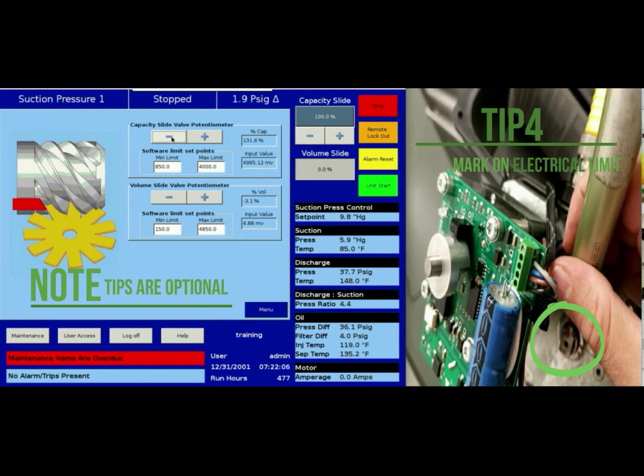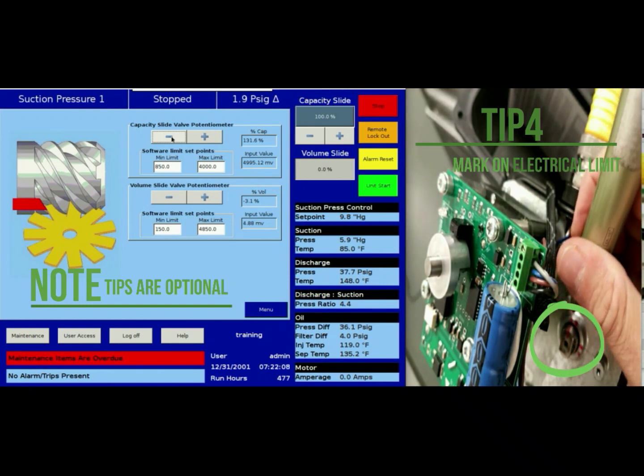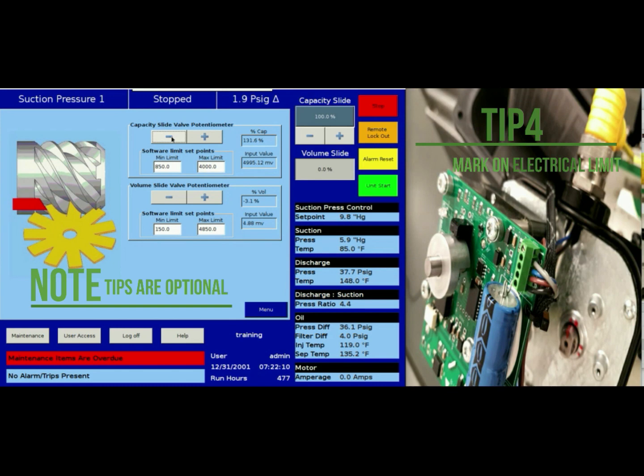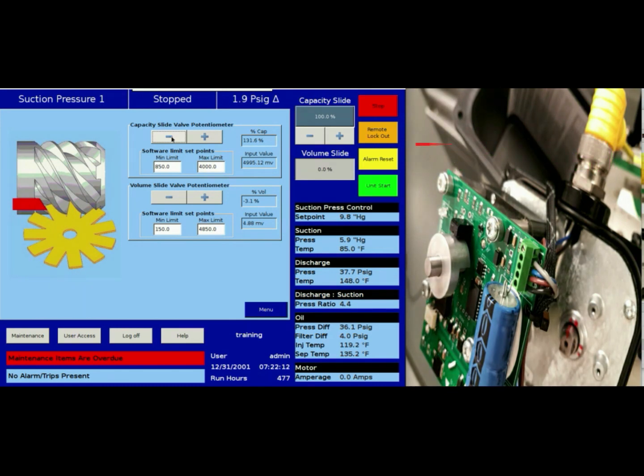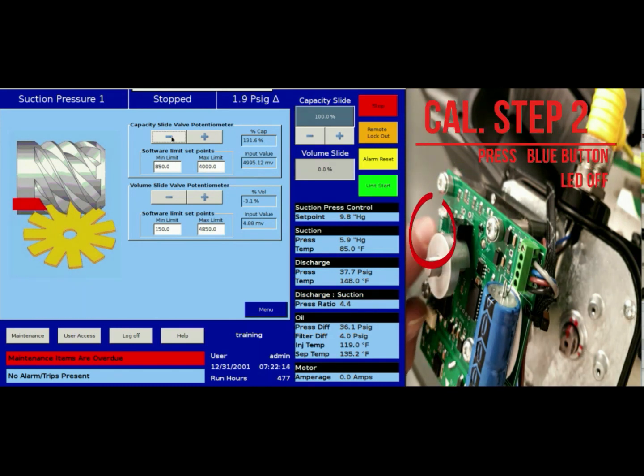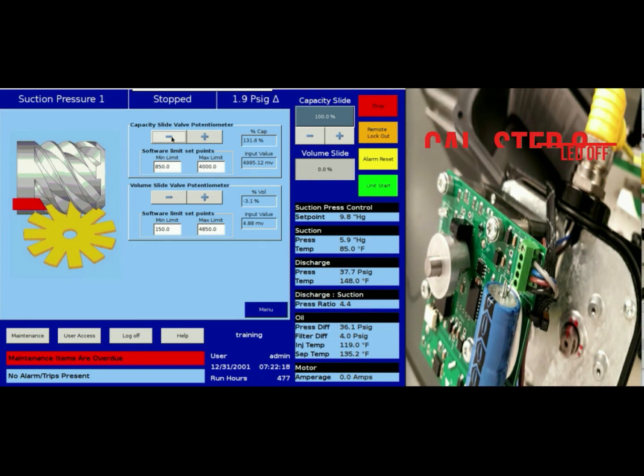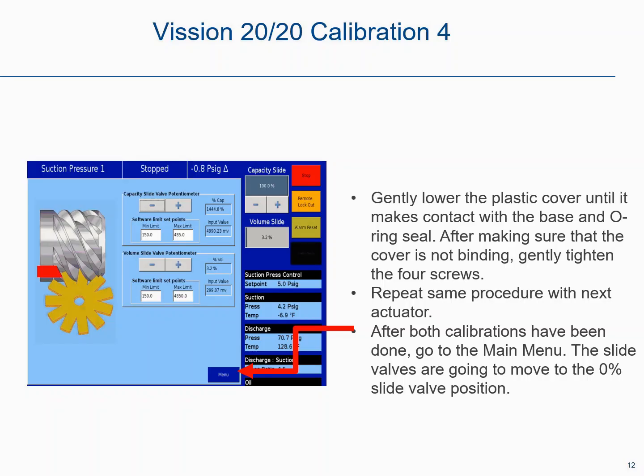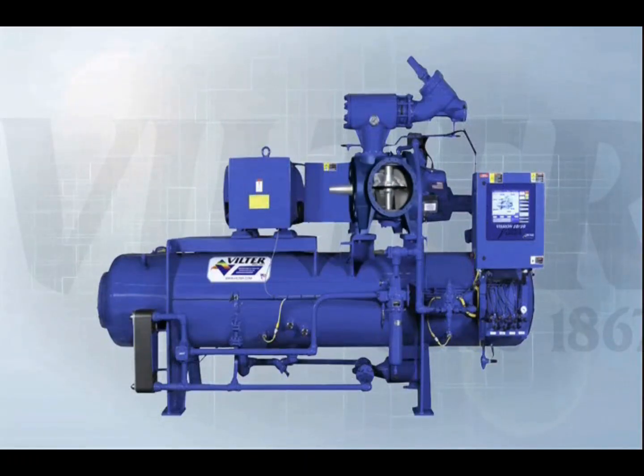Now you can press the blue button on the actuator one more time. This will stop the LED blinking and your actuator has now been calibrated. Repeat the same procedure for the next actuator. Once both actuators have been calibrated, gently lower the plastic cover over the base and gently tighten the 4 screws evenly, ensuring that the actuator cover goes on correctly, not allowing moisture to get inside.